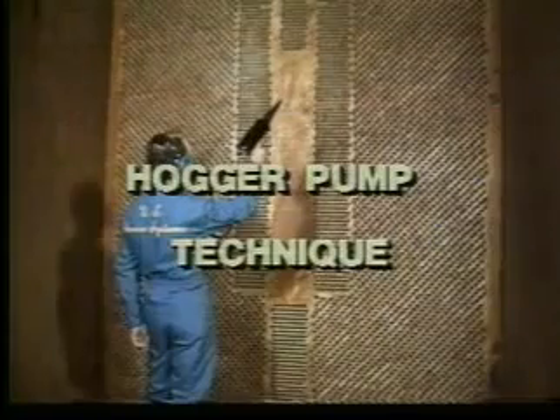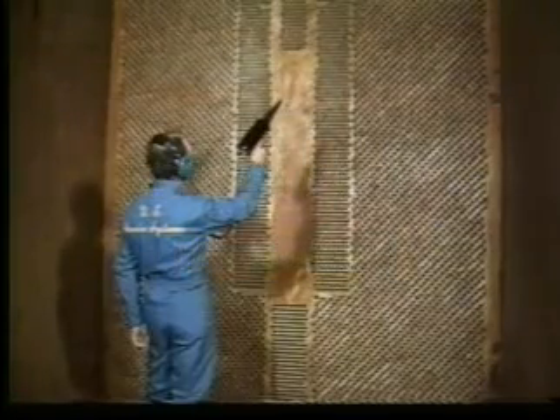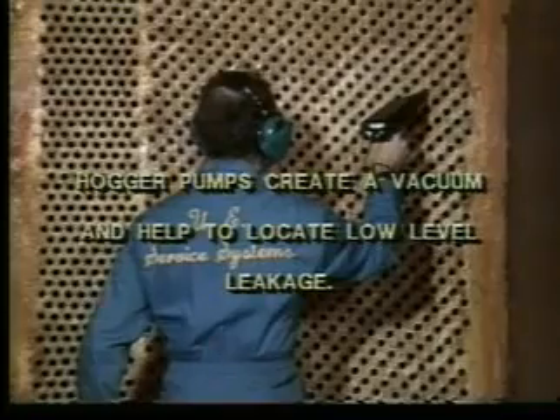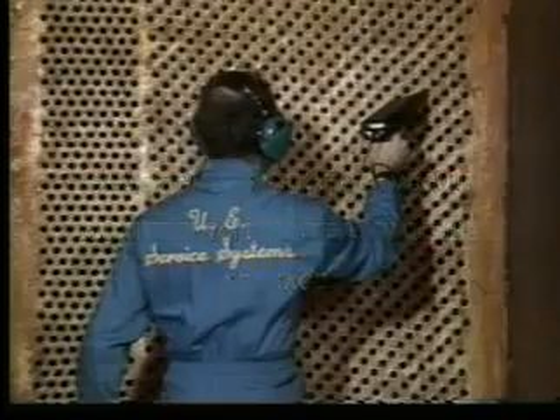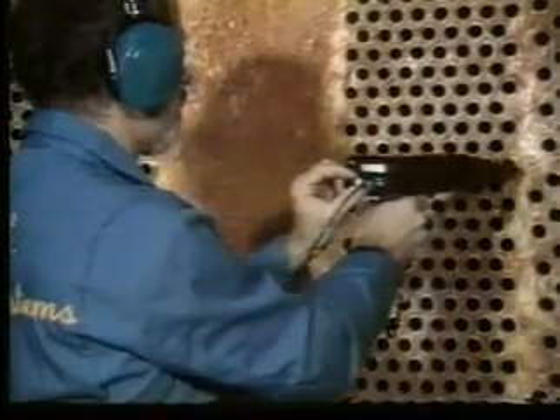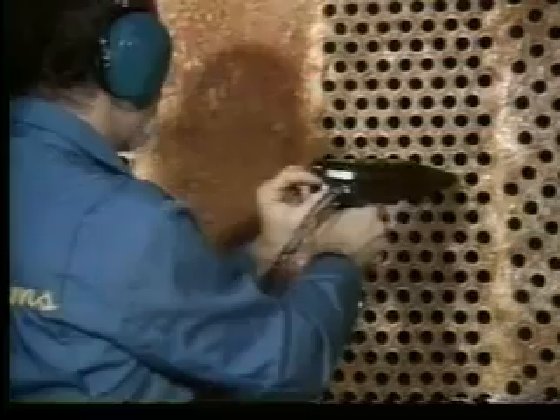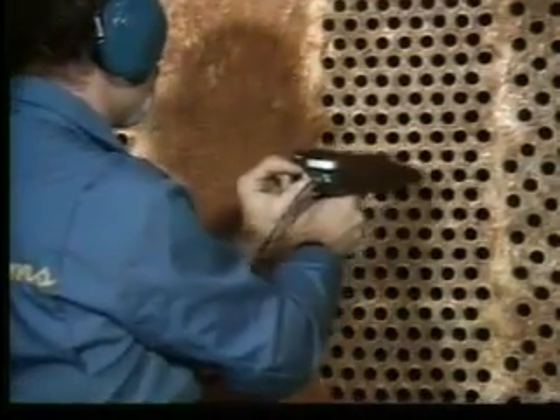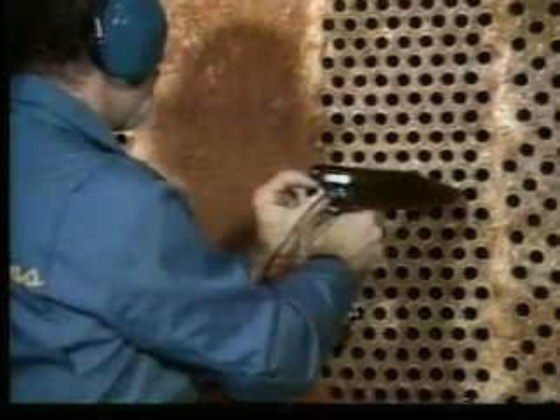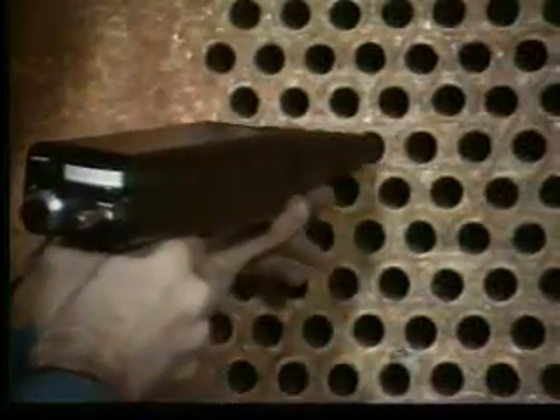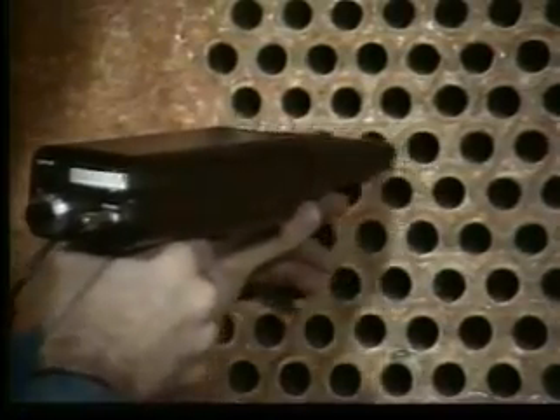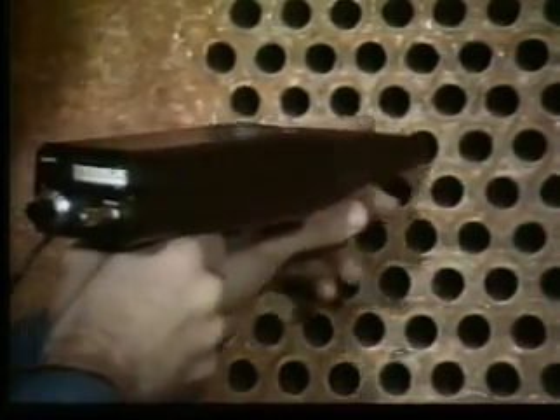One last technique for locating a leak site should be mentioned. It is highly effective, but can only be conducted during an outage. Use Hogger pumps to generate a large vacuum on the steam side. Then scan inside the inlet and outlet tube sheets for leak sounds. The speed, accuracy, and ease of the ultraprobe will help you locate costly leaks, making it well worth your efforts in the initial startup of your testing program. You will soon see why the ultraprobe ultrasound method is rapidly becoming the method of choice for leak detection.